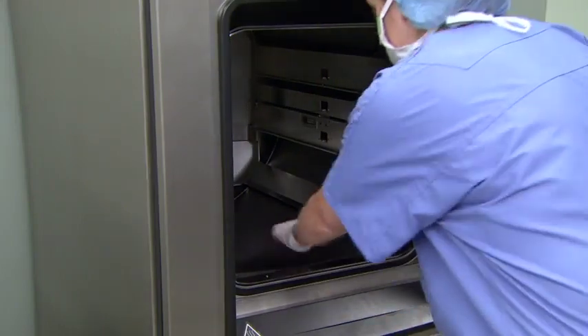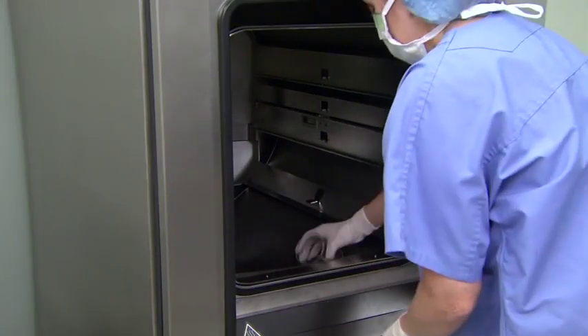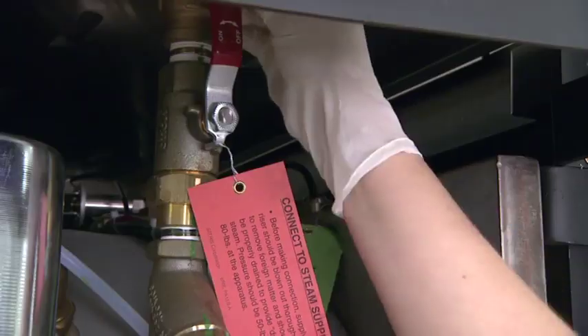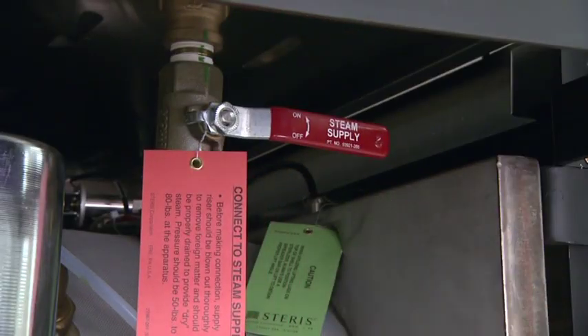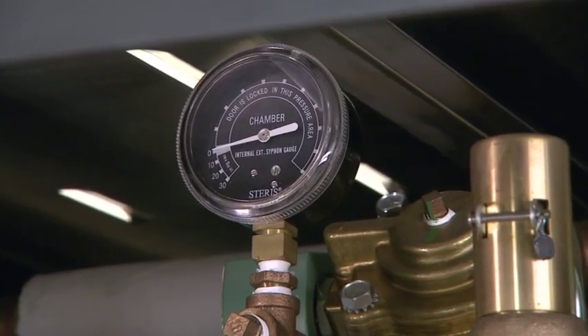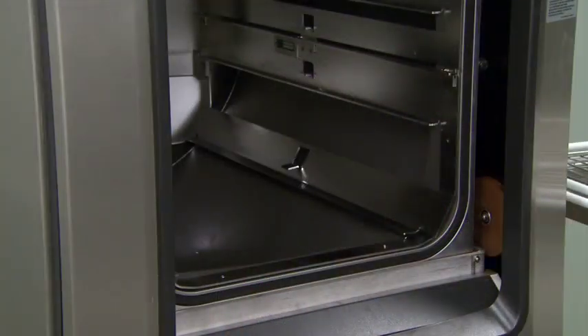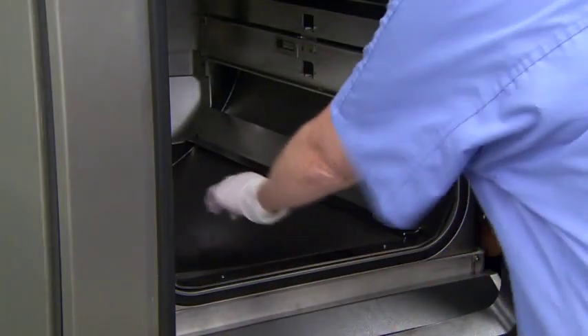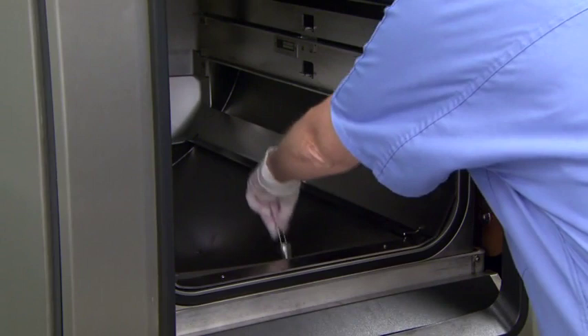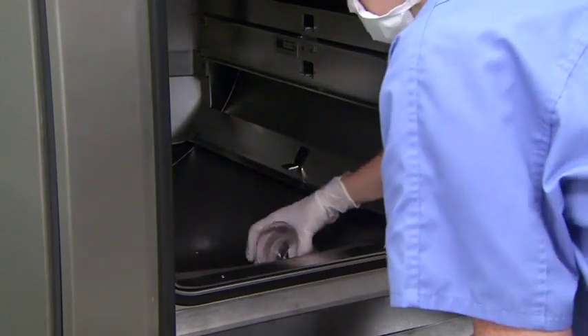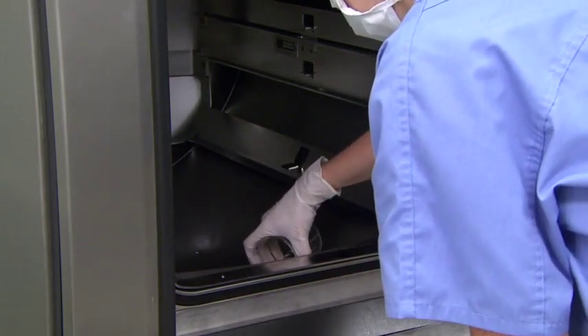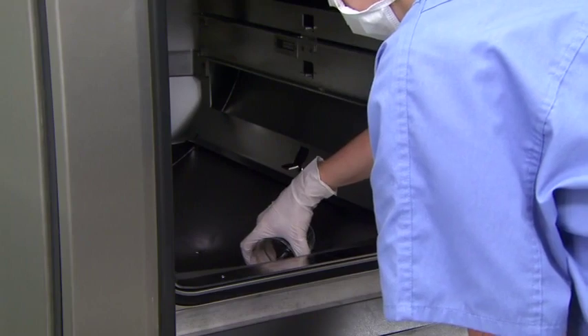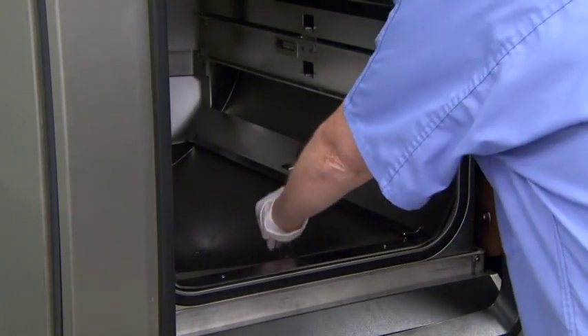Once a week, or whenever the line becomes clogged, you'll want to flush the chamber drain. To do this, turn off the steam supply valve. Wait until the jacket pressure is 0, and wait until the chamber has cooled to room temperature. Remove the chamber drain strainer. Pour a solution of 1/4 cup of instrument detergent and 1 pint of hot water into the drain, and place the strainer back in the drain.